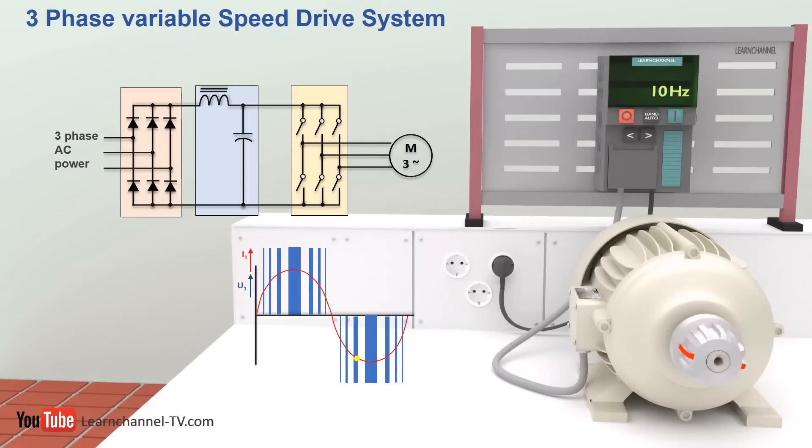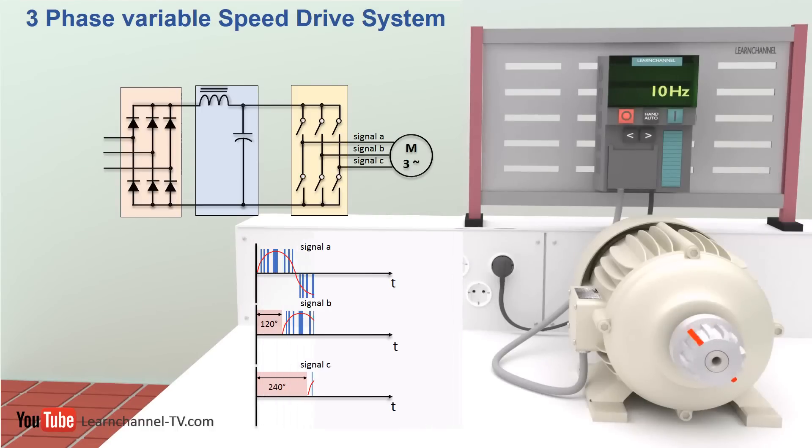The inverter output is not a true sine wave but an approximation based on PWM or Pulse Width Modulation. This Pulse Width Modulation scheme works because the motor coils are large inductors which do not allow current to pulse like the voltage.